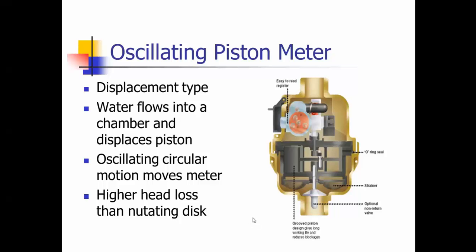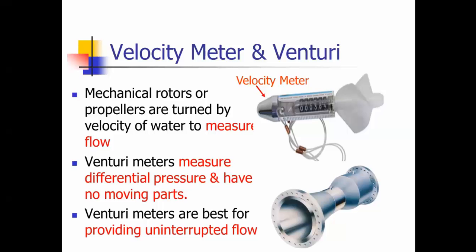This is an oscillating piston meter. It's also a displacement type meter, and the water flows into the chamber, and that causes that piston to move up and down, and then that's what turns the totalizer. There's a higher head loss than a nutating disc. This is a velocity meter. You can see the propeller on there as the water passes through it, turns a totalizer.